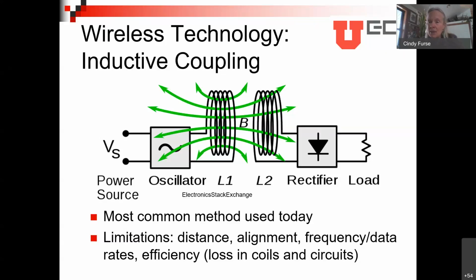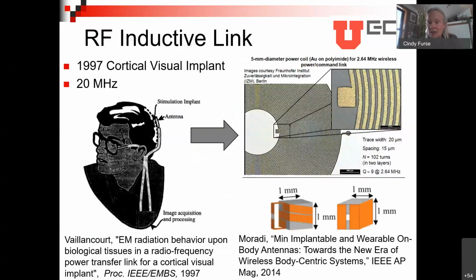But there have been improvements in the inductive link, and you'll see these throughout the electromagnetics community and still more coming. One of the first was being able to do printed inductors so that you could have many, many coils in a very small area. These are pretty good, a little bit of loss of efficiency because of loss in the printed metallic materials, but not bad. These are pretty good inductors. The one down at the bottom is making the inductors even smaller. So this is a 1 millimeter coil where it either had a C-shaped coil or a little wraparound to be able to be used for very small implants. Not a very efficient device, but a very, very tiny one.